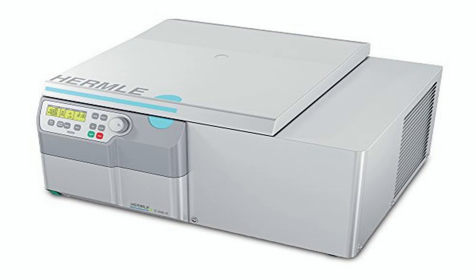Conversely, if you're a teaching lab that spins down a handful of tubes per class, a startup with limited bench space, or a hobbyist who only needs occasional centrifugation for simple protocols, the Z446K may be overkill. The refrigeration system draws more power than a non-cooled unit, and the larger footprint could crowd a cramped bench. In those scenarios, a basic benchtop centrifuge without a cold chamber, perhaps one that takes fixed angle rotors, will meet your needs.